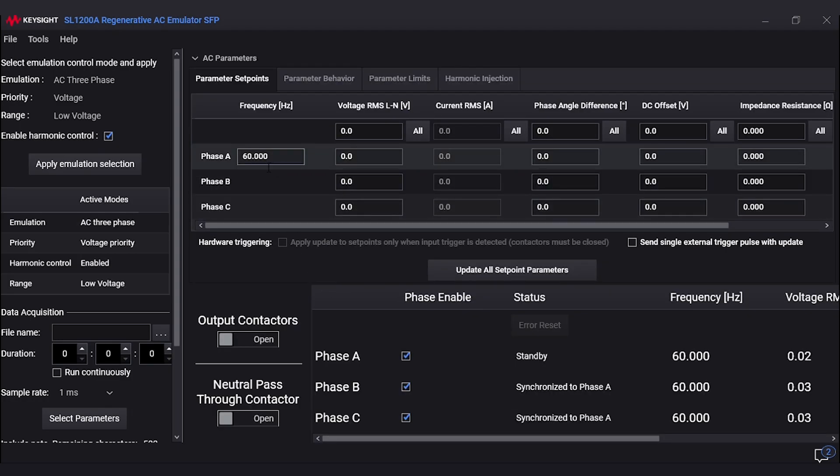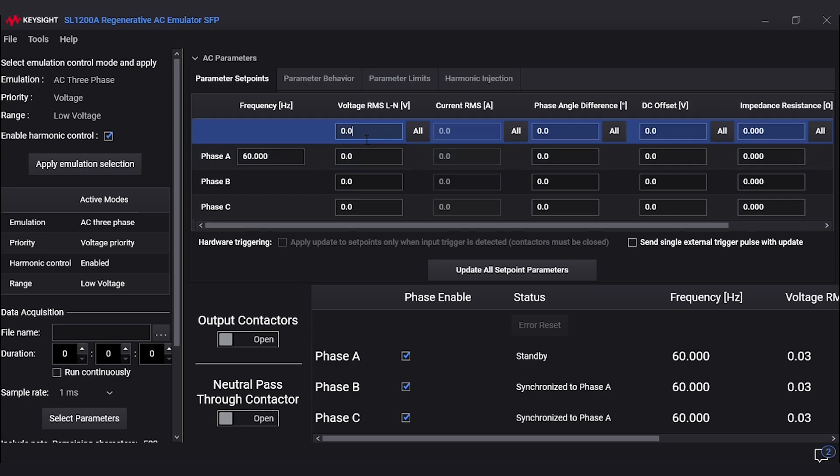The second setting to look at is the line-to-neutral voltage. This software does not calculate the line-to-line voltage for three-phase loads, so you will have to calculate the line-to-neutral voltage. Then do the math to make sure it's within the specs for your load.